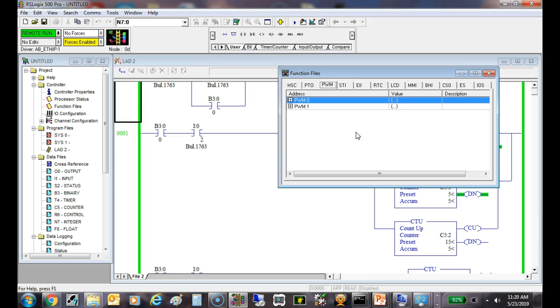So we could actually output pulse width modulation directly off this PLC. And some of your variable speed drives, if the variable speed drive runs off a PLC, it sets the speed through pulse width modulation. The pulse width modulation feature is going to be on most PLCs. Now, this PLC can't really do it because it runs relay outputs. We can do it, but it has to be real slow. So we'll try to show you all that.